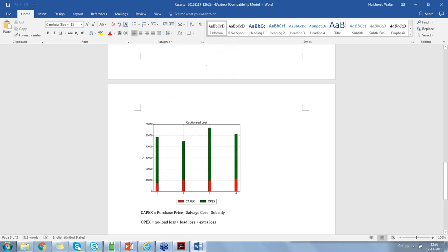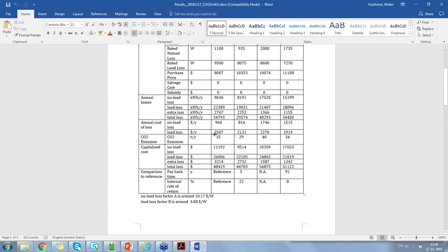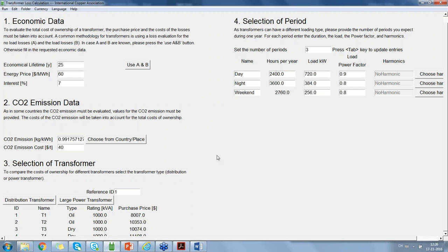What I would like to ask you is to take into account the values of the total extra losses which we calculated in this situation. I've added them over there, and I would like to show you what the impact is in case we're adding some harmonics to the transformer. If we go back to the transformer tool, we said, okay, we haven't added any harmonic loading to the transformer, but of course we can select a harmonic loading on the transformer and see what the impact will be.